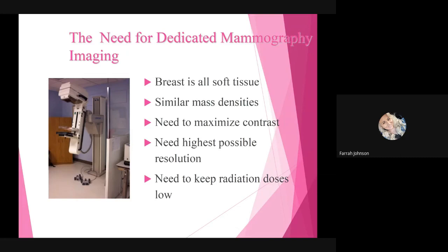So, the need for dedicated mammography imaging. Well, breast is all soft tissue. Typically within the breast tissue, you're going to have similar mass densities, which develops a need to maximize contrast. We also need to be able to have the highest possible resolution because we are looking at very, very fine structures within the breast tissue. However, we do need to keep radiation doses as low as possible because we know that the breast tissue is radiosensitive. That is what all led to the development of dedicated mammography machines.